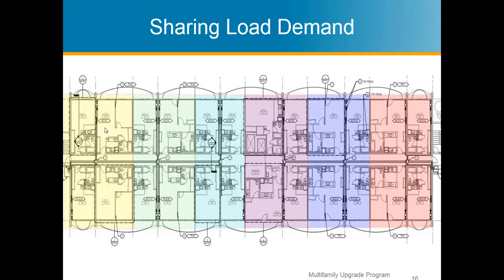So it seems simple enough, but it's something that you need to really consider. If you get a set of plans and you see that your client's mechanical engineer may be putting in these systems, that the design intent of those systems is to share load, but they have all of the same units off one selector box that's all facing north, then you're not really reaping the benefit of that shared load demand mentality that it's intended for.